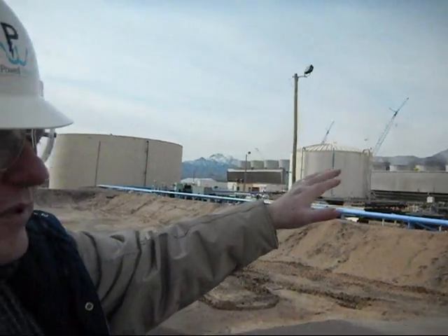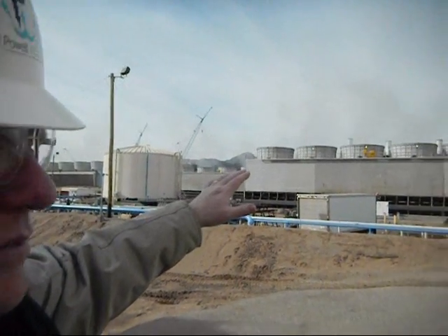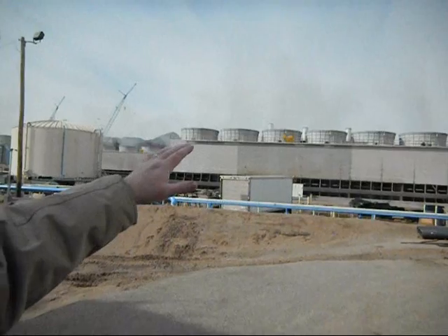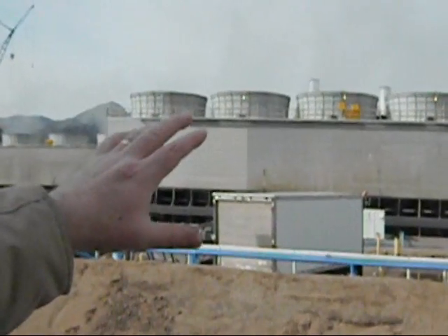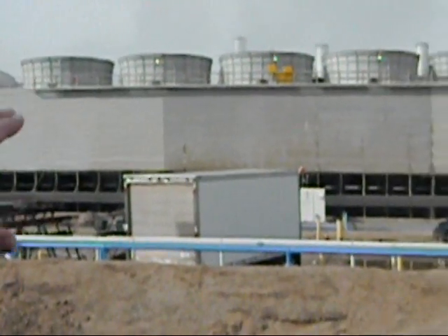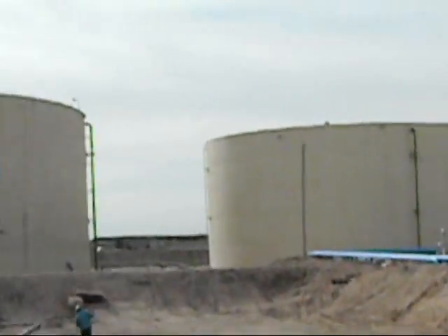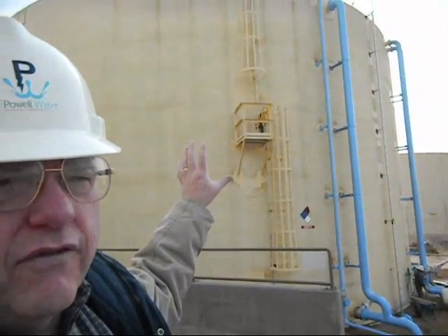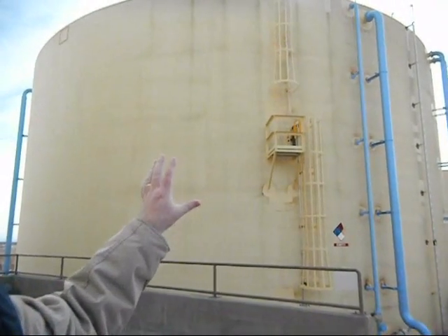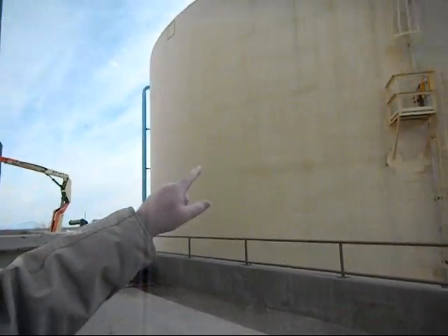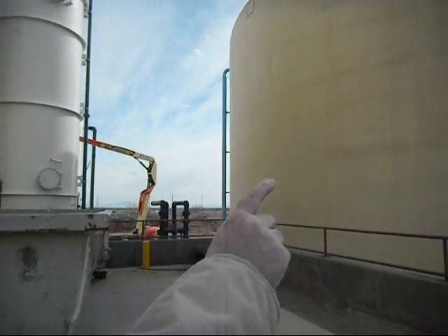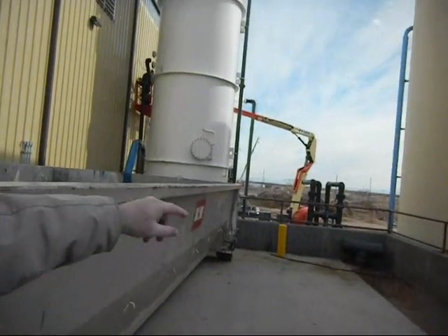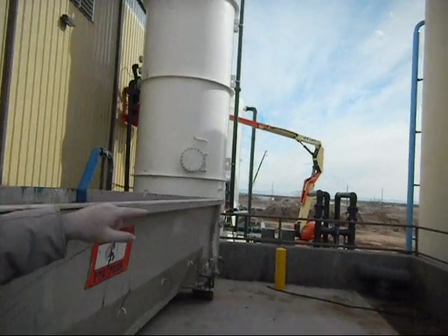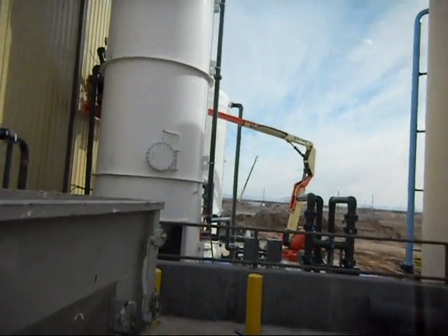Okay, the water concentrates in the cooling tower, and when it gets to 200 parts per million of silica, then they have to throw the water away. That water is called blowdown water, and it is now transferred into this tank behind me as a feed tank to our electrocoagulation system. The water will come out of the surge tank and be pumped into the building to feed the electrocoagulation unit.